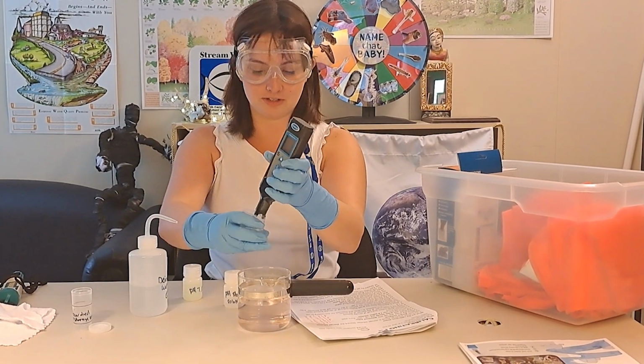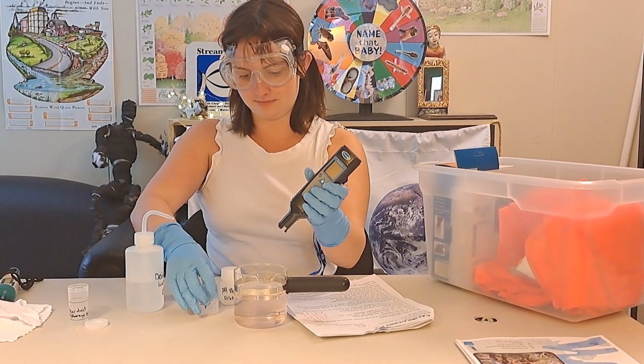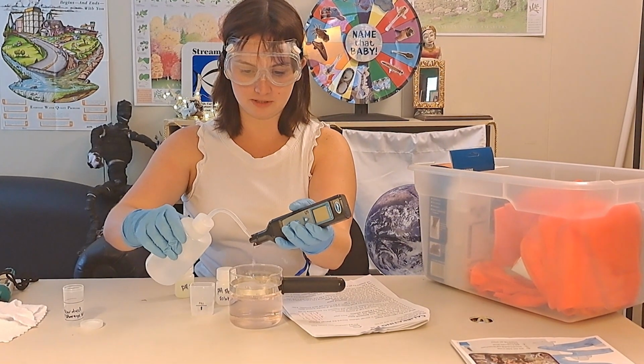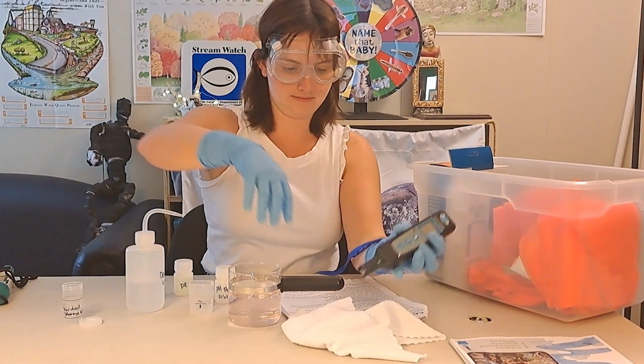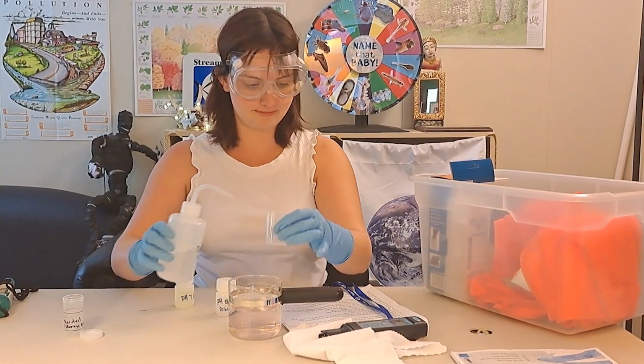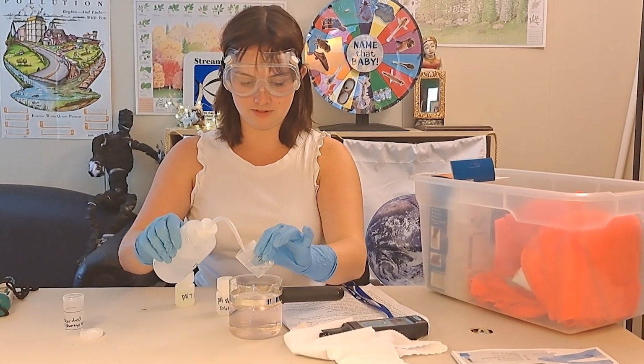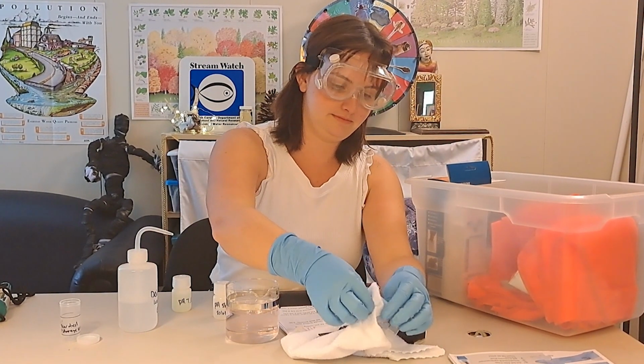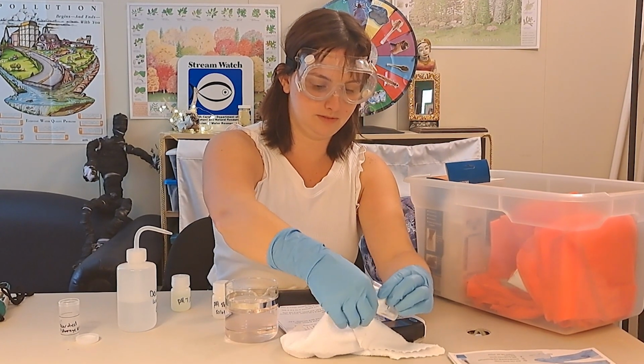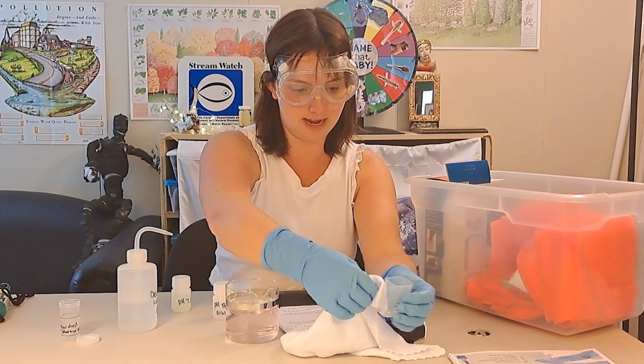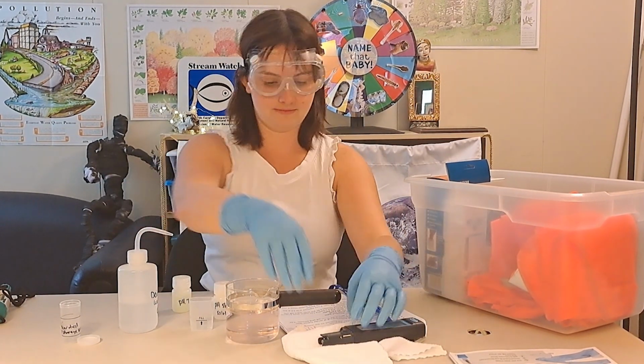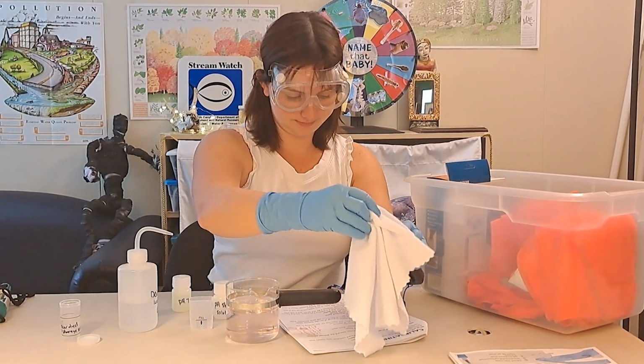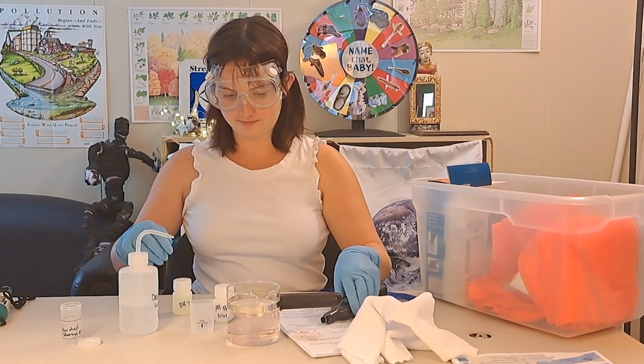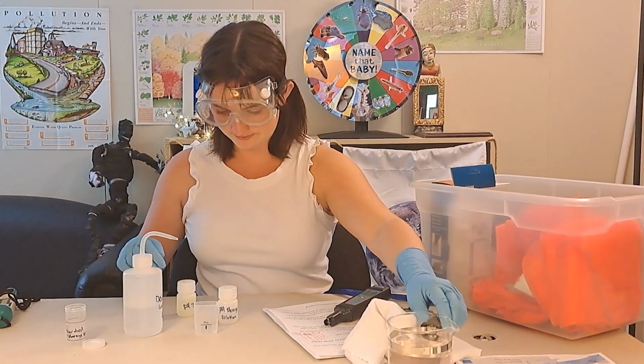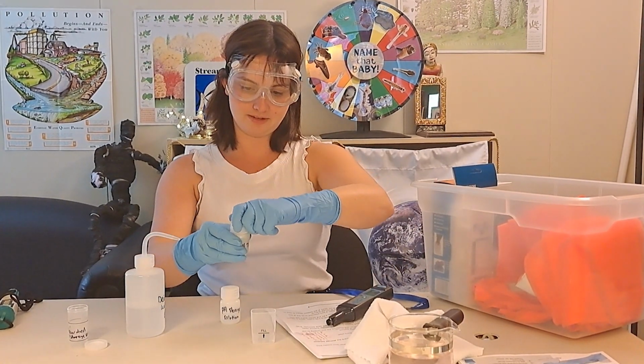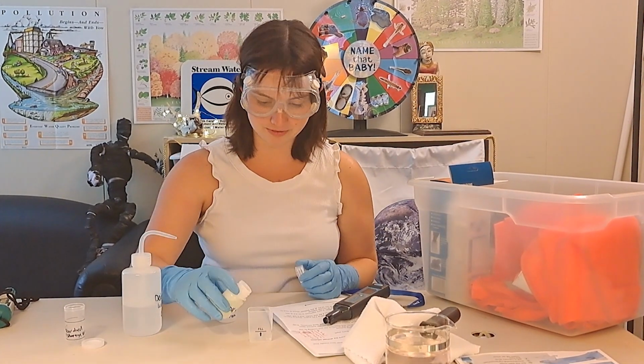Your first step will be to discard the used solution and to rinse the pen with deionized water, and also the cap, so that it's ready for the buffer. Whenever you dry this equipment, you'll try your best to dab it instead of rubbing. We're done with this for a second. So now we fill the cap to the fill line with pH 7 buffer.